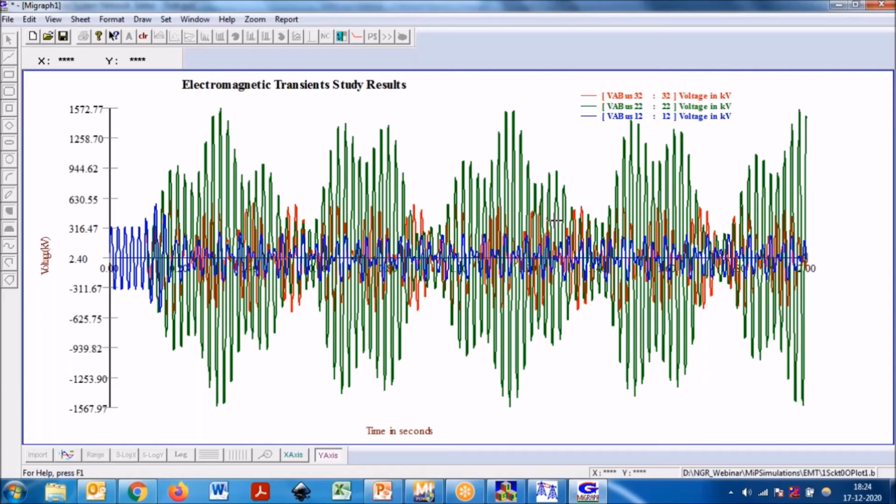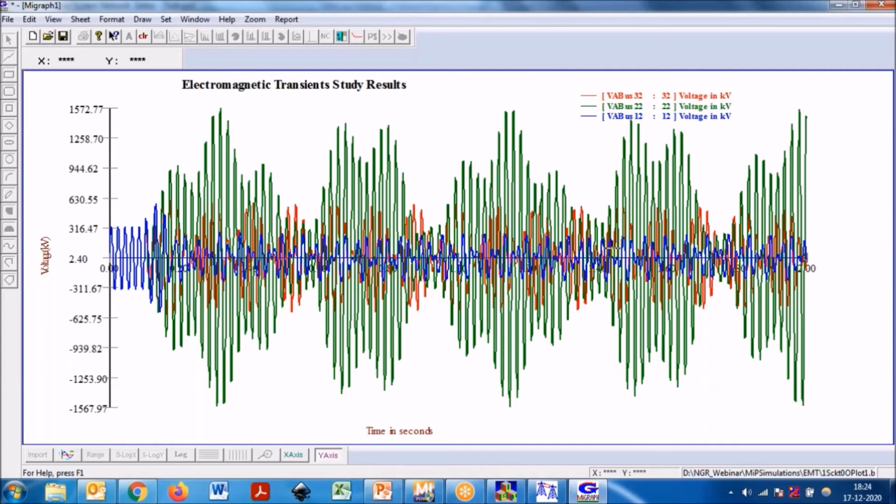Next we can see the red one. It is a little higher than your rated value, but because we have used only a very small 2.5% value, and that value is valid for single phase switching, whatever the formula. But this is not able to completely handle your two phase opening resonance point.